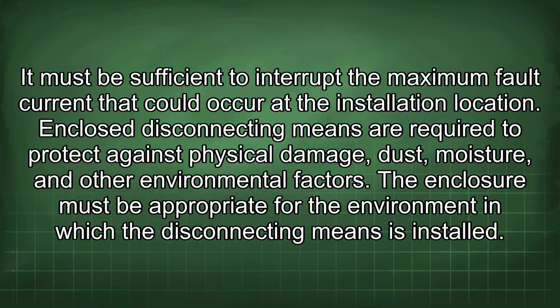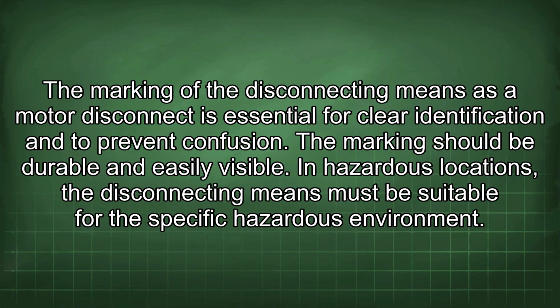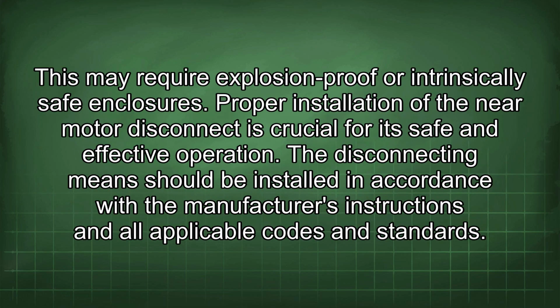Enclosed disconnecting means are required to protect against physical damage, dust, moisture, and other environmental factors. The enclosure must be appropriate for the environment in which the disconnecting means is installed. The marking of the disconnecting means as a motor disconnect is essential for clear identification and to prevent confusion. The marking should be durable and easily visible. In hazardous locations, the disconnecting means must be suitable for the specific hazardous environment. This may require explosion-proof or intrinsically safe enclosures.